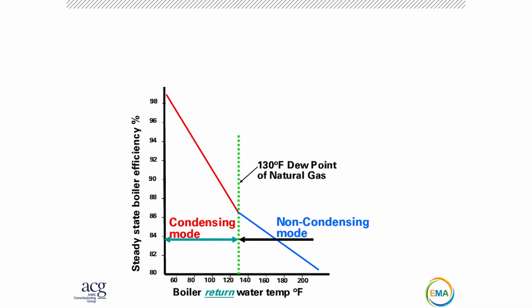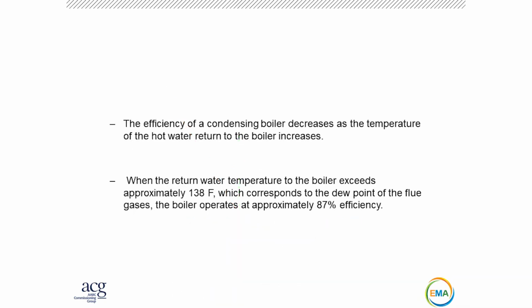Yep. So here's just a little quick graph so you can kind of see the boiler return water temperature across the bottom, boiler efficiency going up. And if your return is above 130, your efficiency's in the 80s, give or take, mid 80s. And once you hit that dew point, that's when the efficiency really starts to take off. And the colder the water, the more efficient you are, because the more you can create the condensate, which then extracts that heat that would normally go out the stack. So, again, key point. I mentioned this already, that return water temperature is huge.